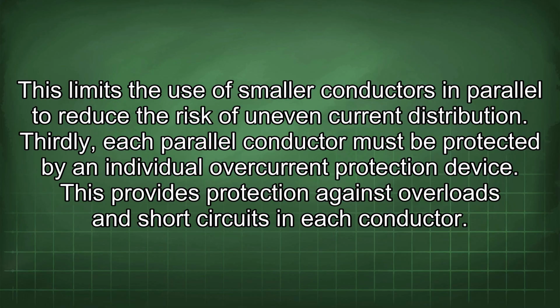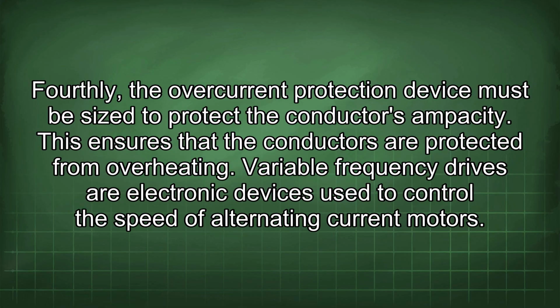Thirdly, each parallel conductor must be protected by an individual overcurrent protection device. This provides protection against overloads and short circuits in each conductor. Fourthly, the overcurrent protection device must be sized to protect the conductor's ampacity. This ensures that the conductors are protected from overheating.